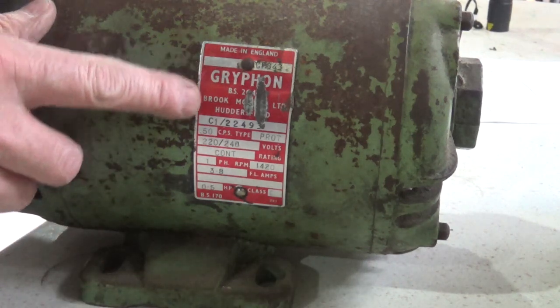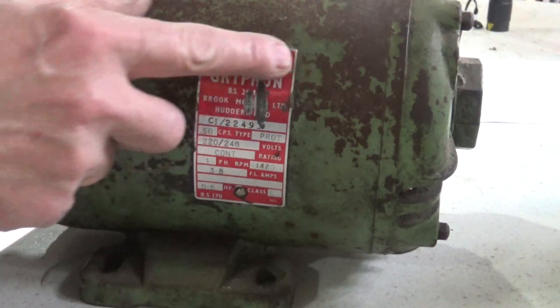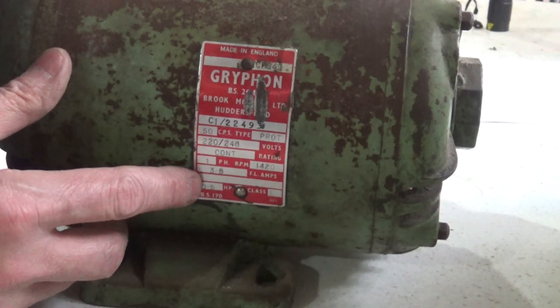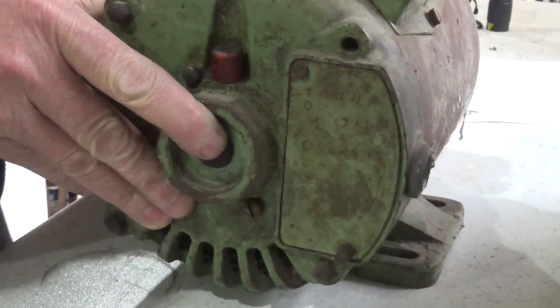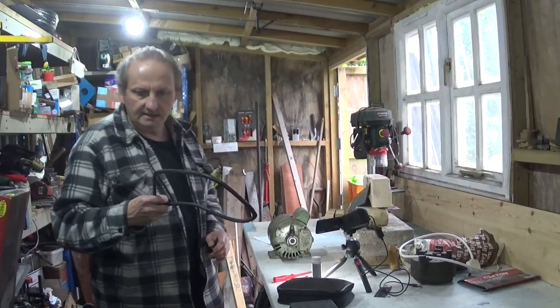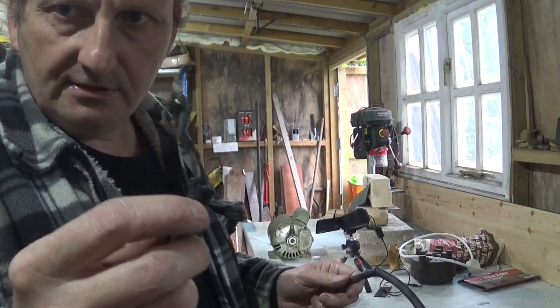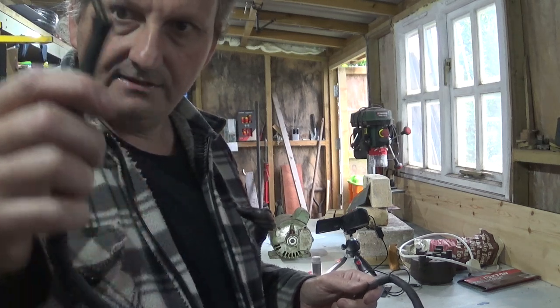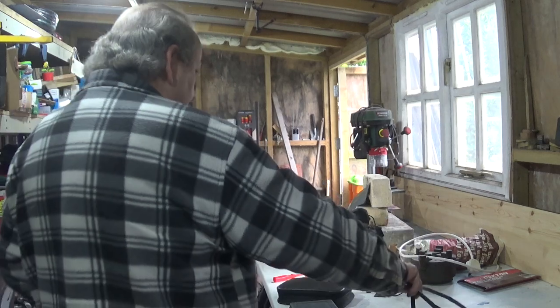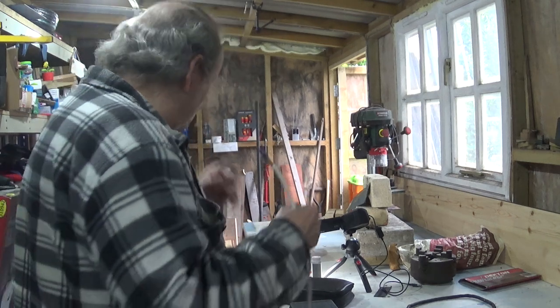I've cleaned the main plate off and you can see it's a Gryphon — quite a lot of that's wiped out — made by Brook Motors of Huddersfield. It's a single phase half horsepower motor. The reason for rewiring is because the old cable's insulation no longer meets current safety standards. So I've made up a new wire with ends on it.